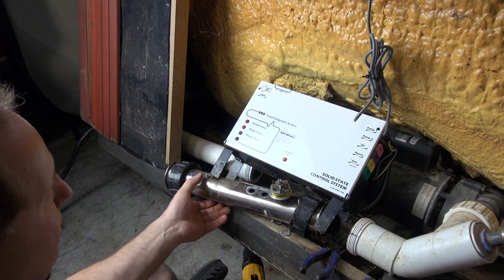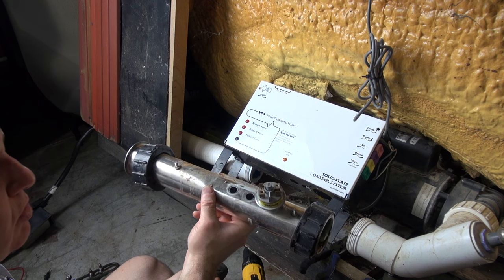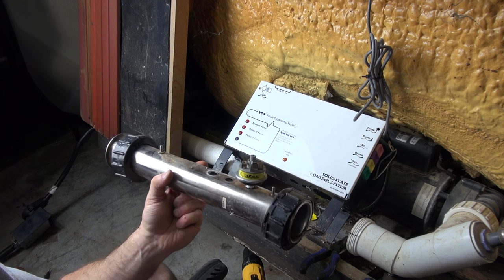Like that and this heater is pretty damaged looking but where it was leaking through is it leaks through the epoxy right here and it actually leaks through to the front so you can see that it's rusty right there. That is a bad heater element. Now I'm going to turn the camera off, go clean this tube up and get it ready and then I'll show you how to install it. Stay tuned friends.